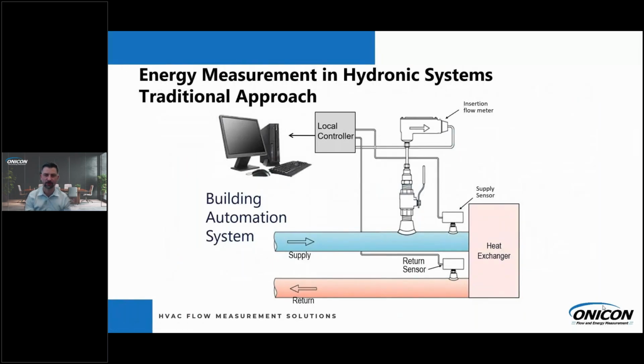I'd like to talk a little about the story of how ONICON got into BTU measurement. If you think back to the early 90s, we only sold flow meters, and we might get a phone call 3 years after shipping one, and they'd say, hey, your flow meter's wrong. And we'd say, well, we calibrated it for your specific application. Why do you think the flow meter is wrong? They'd say, I'm using this for BTU measurement and my BTUs aren't adding up. Maybe they're just using an ONICON flow meter and 2 temperature sensors back to their building management system to calculate BTUs. So ONICON really dove into understanding where these inaccuracies were coming from.